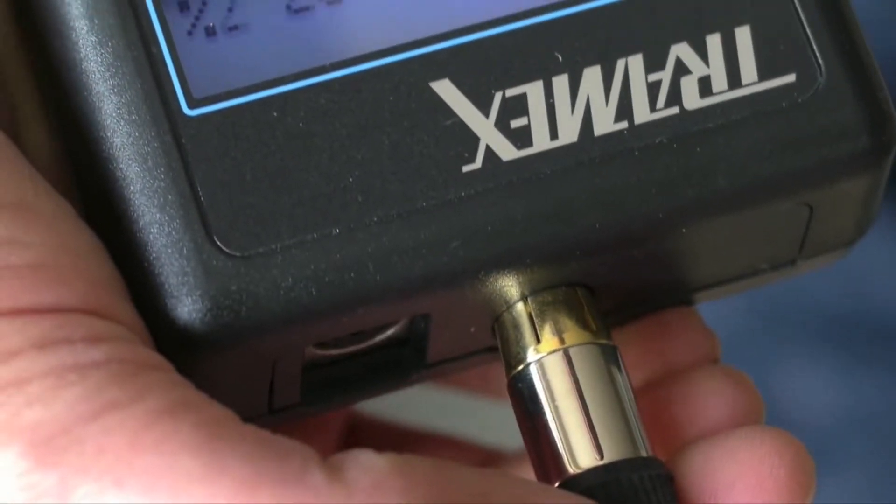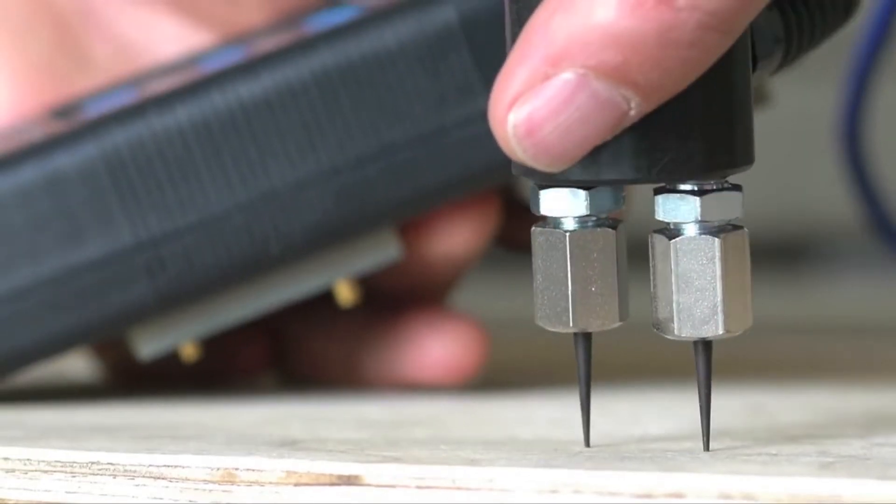The CMEx can also be used with the handheld pin probe for measuring moisture in wood. This is especially useful when installing wood floor coverings. By comparing the moisture content of wood with the ambient relative humidity conditions, we can determine when the wood is in balance with the ambient conditions within the building.